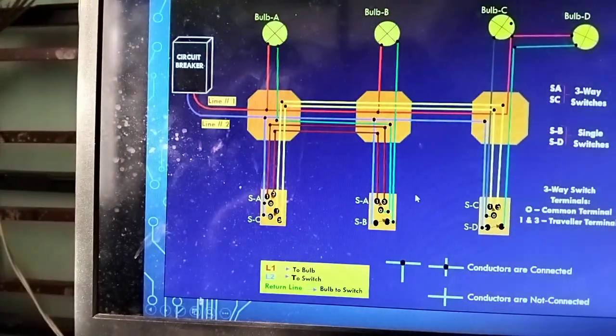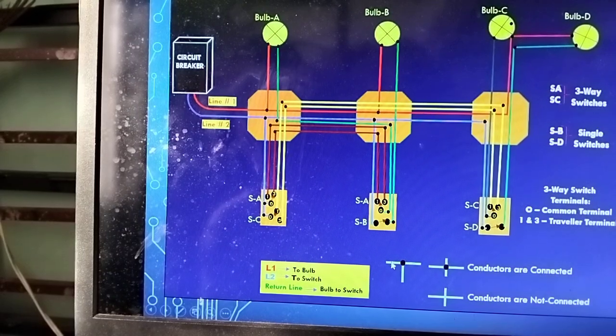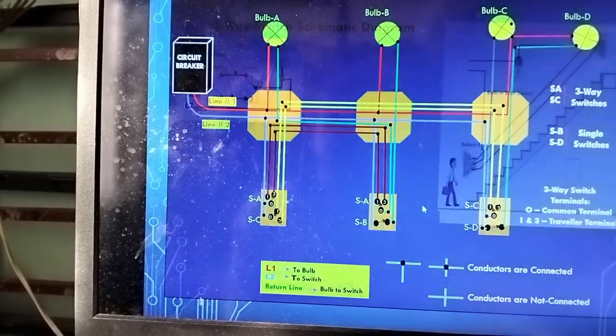And on the electrical code here also, I just want to remind you, if you notice, like this is a connected wire. If it is only crossing without a dotted line, the wire is not connected, like this. It's crossing on this line, so it is connected here only. Same thing here, the blue for switch B. This is line 2 for switch B. So where does it go? It goes here and goes straight, and then the other line is connected to line 1, so you can turn it on. Okay.